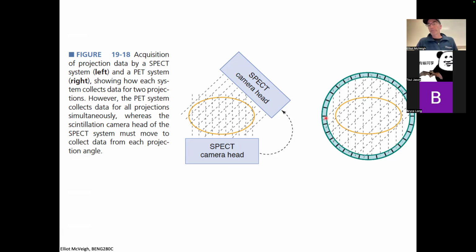And if I look down my whole list and say, okay, what about this one and this one? That gives me another line. I can create a projection function at a specific angle just by looking at detector pairs and where their coincident events occurred. So after I collect all my data, we just go through the list and create these projection profiles from that list mode data.